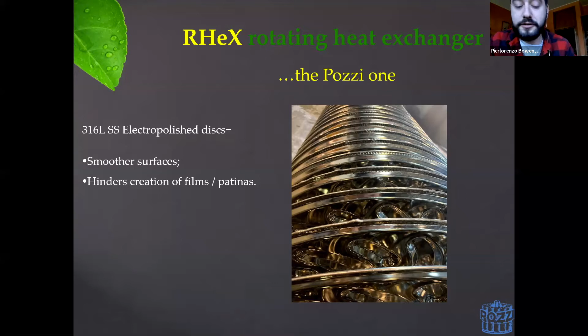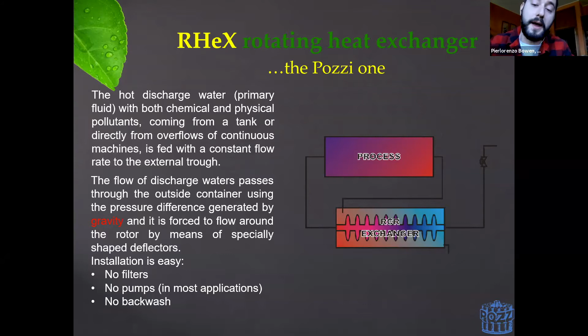Generally, the process works like this. You have your process, which could be, for example, dyeing or bleaching or mercerizing, whatever, and you're going to have a hot discharge. This discharge can go by gravity, so no requirement for pumps and no requirement for any filtering station. And it will go directly to the exchanger. Then you will not need any backwash or any external cleaning system for the exchanger, which will preheat your water and feed it back to the process.